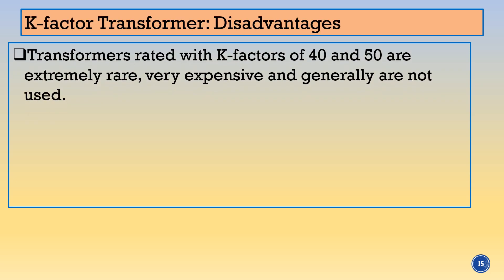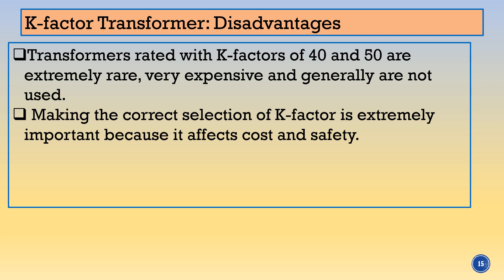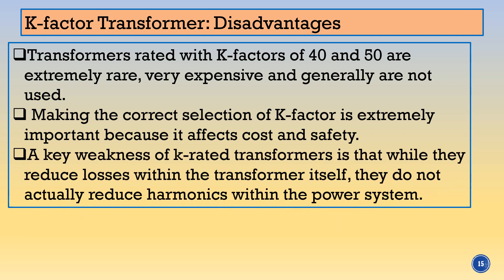What are K factor transformers? K rated transformers prevent overheating of the transformer by accommodating increased stray losses associated with the K factor. They prevent neutral overheating by oversizing it at 200%, which is more economical than using the derated approach and is more efficient. A key weakness of the K rated transformer is that while it reduces losses in the transformer itself, it does not reduce the harmonics — the harmonic current remains as it is in the transformer.